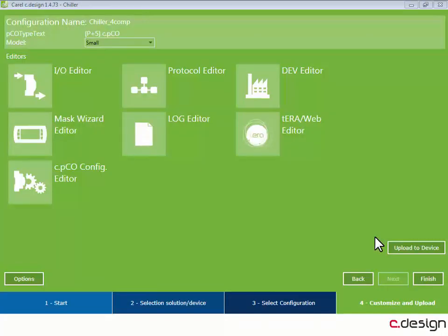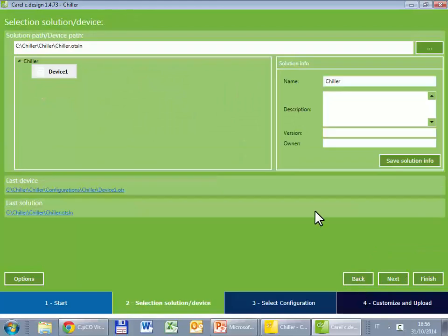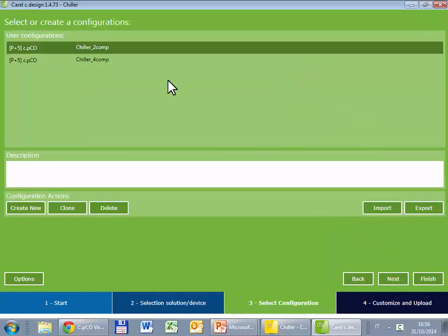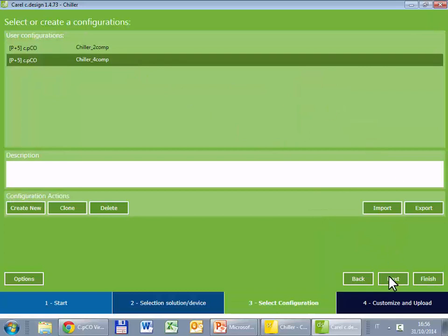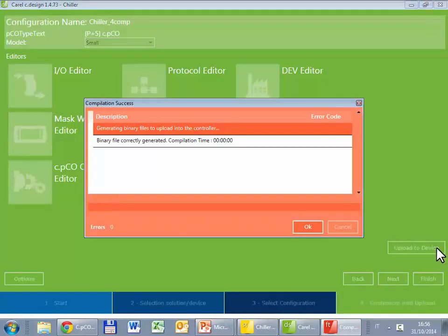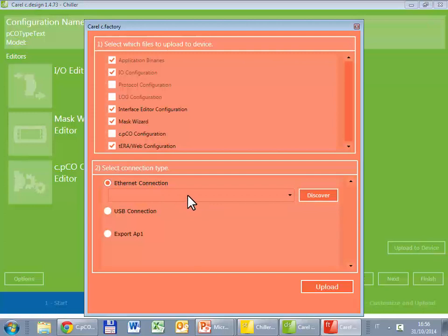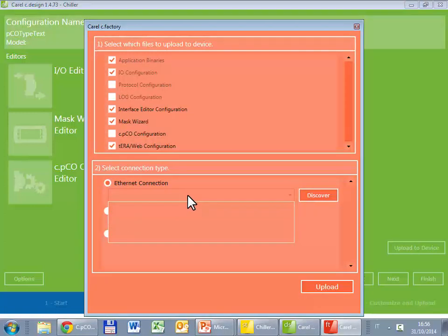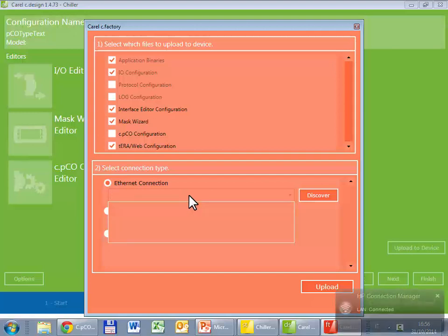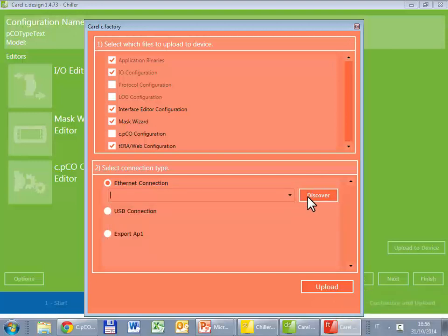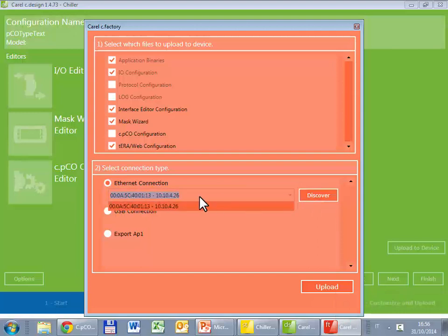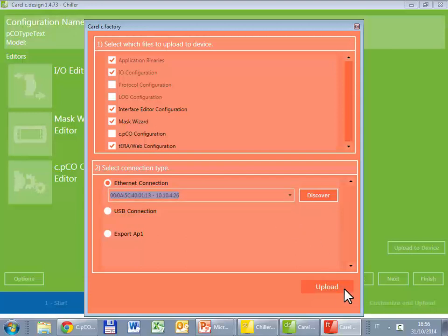Let's go back to Cdesign. We have to check to have selected the right solution, repository, and configuration. And then upload to device. The system starts C-Factory. We have to select the Ethernet connection and select the IP address corresponding to the pCO where we want to install the project. The list is empty. Why? Because just one second ago I have disconnected my PC from the local network. Now I reconnect again. Here should appear the IP address of the pCO that is 10.10.4.26. I can use the discover function, and here is 10.10.4.26. Select that controller and upload.